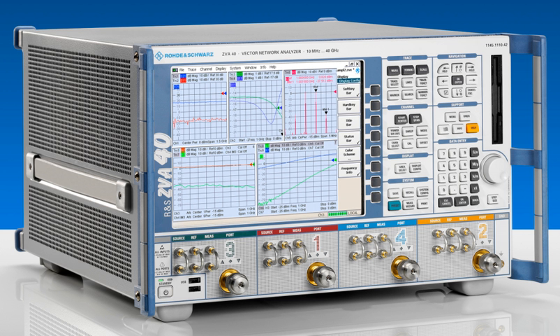The reference port will compensate for amplitude variations in the test signal at the measurement plane. It is possible to share a single detector and use it for both the reference port and the test port by making two measurement passes.